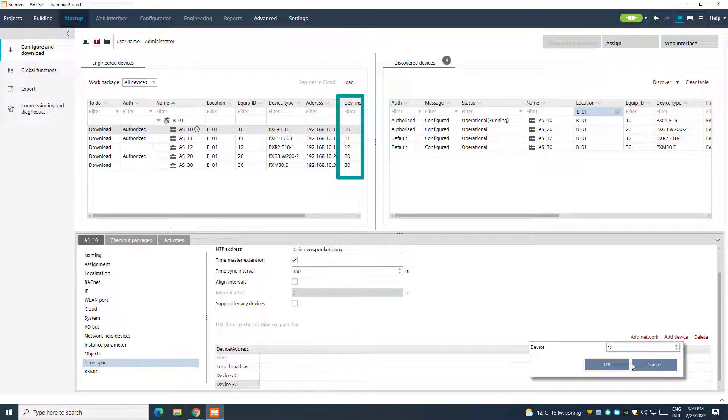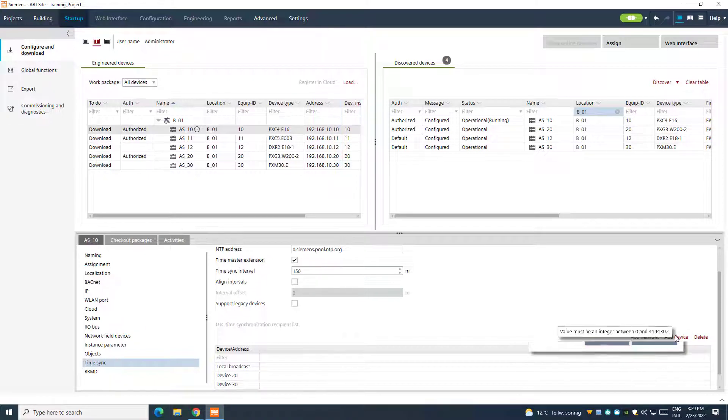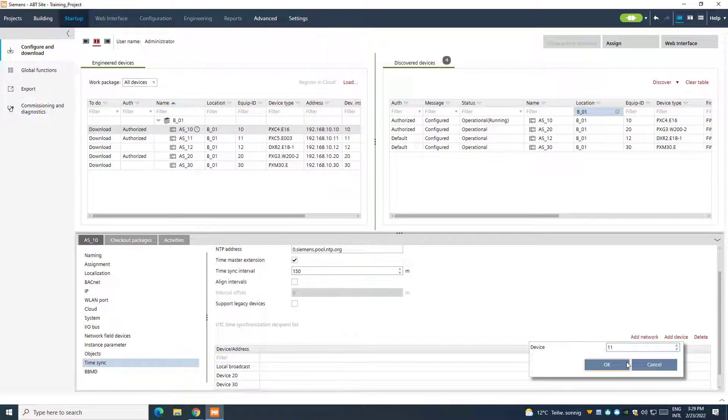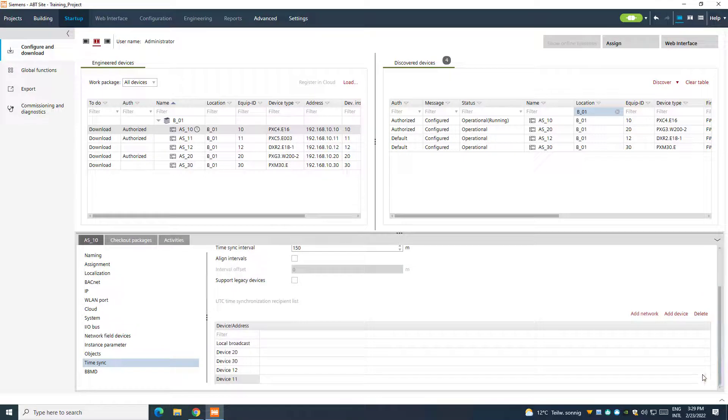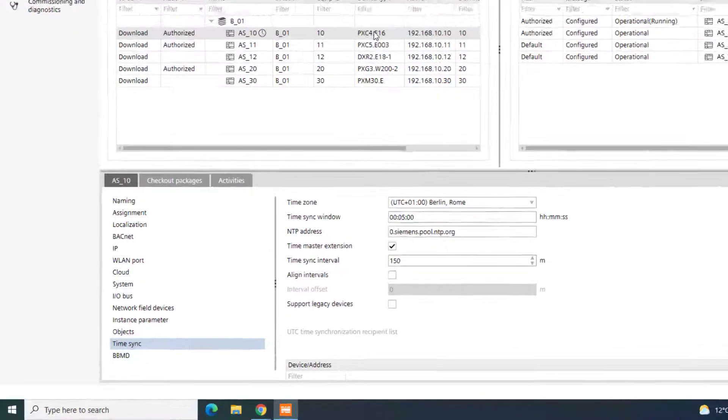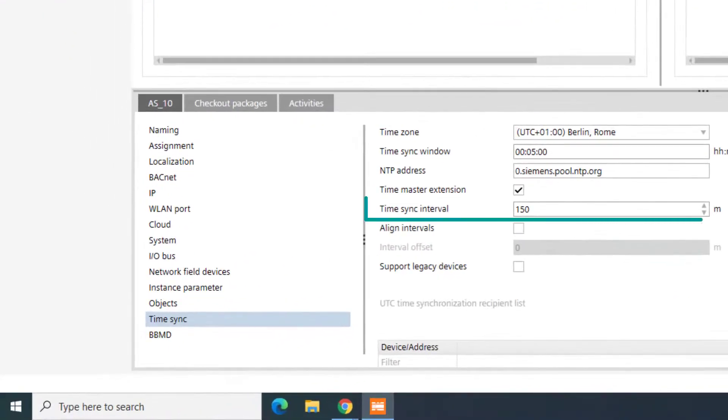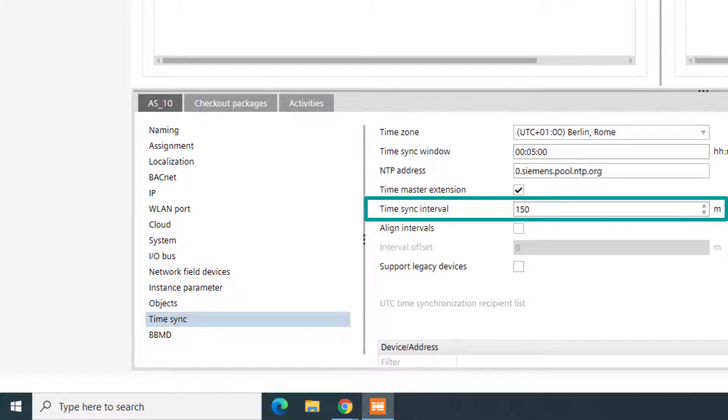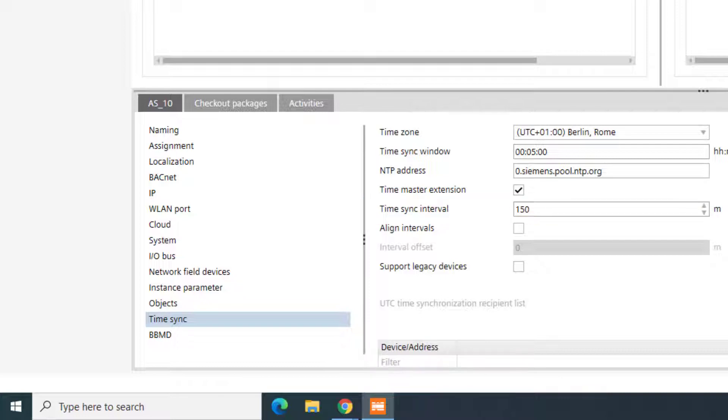If this table has no entry at all, then the synchronization would not properly work. The devices will be automatically synchronized following a predefined interval, which is normally 150 minutes. When it is set to zero, the time synchronization is disabled.